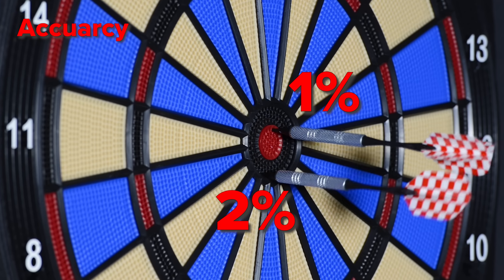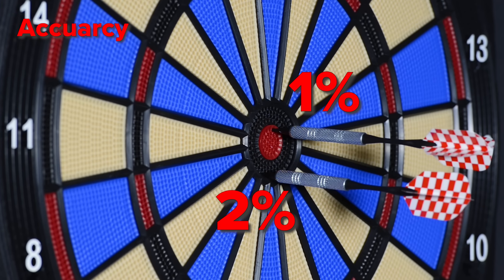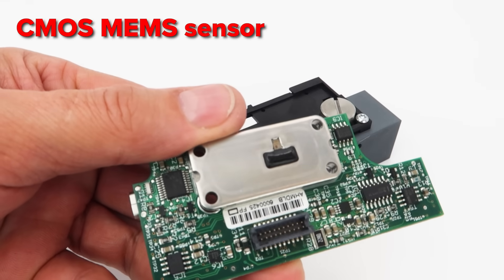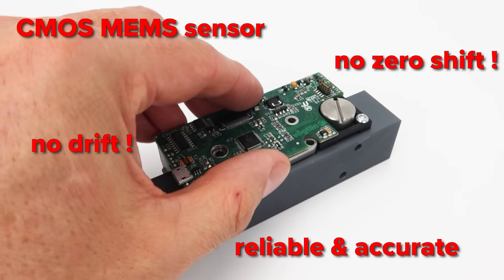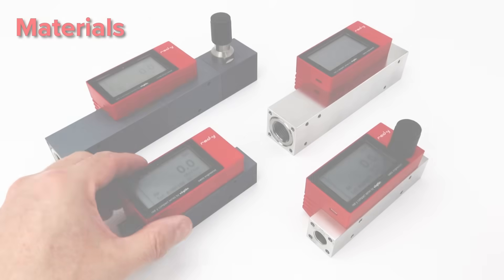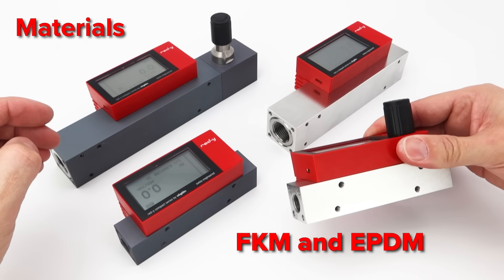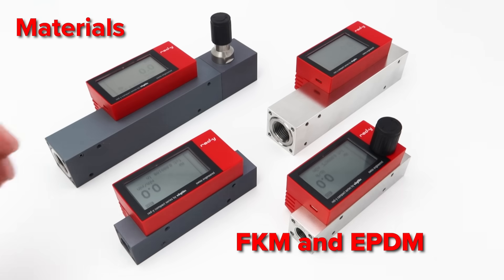The Compact can work up to 10 bar gauge and has an accuracy of two or one percent of full scale, depending on gas and flow rate. A CMOS MEMS sensor warranties long-term stability — no drift, no zero shift, reliable and accurate. You can choose between aluminum and stainless steel, and for the sealing we offer FKM and EPDM. Pressure and temperature compensation is not necessary.